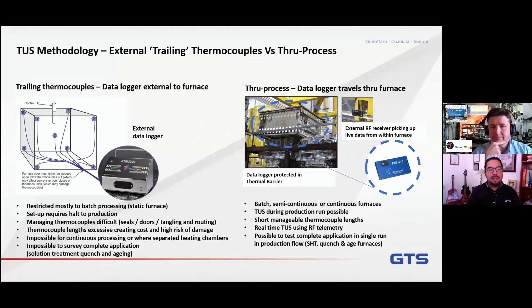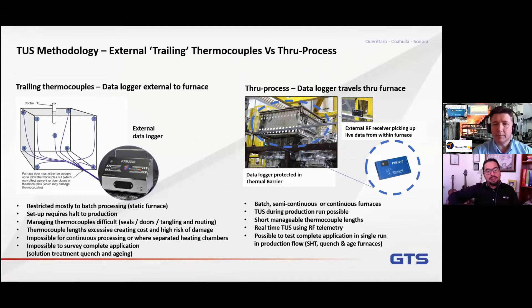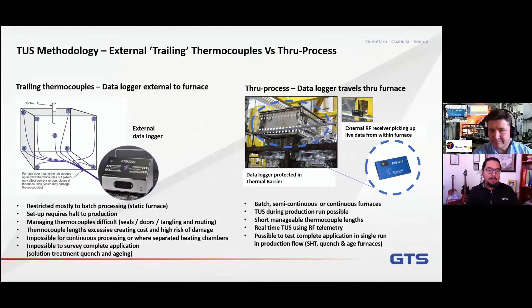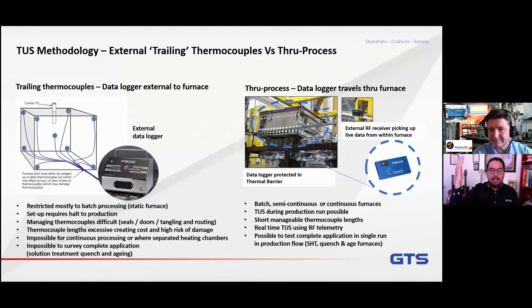For batch furnaces, we usually use an external data logger where we install the thermocouples throughout the volume of the furnace and then pull those thermocouples out and hook them to the data logger. But sometimes when we have a continuous furnace, that's a little bit difficult because we have product moving and doors closing. So trailing thermocouples are probably not the best idea.